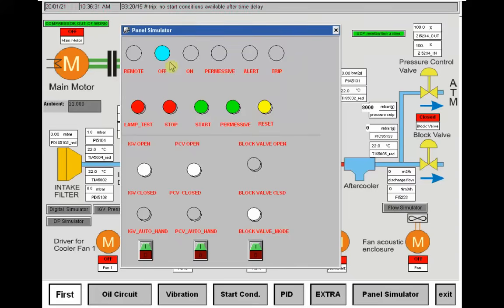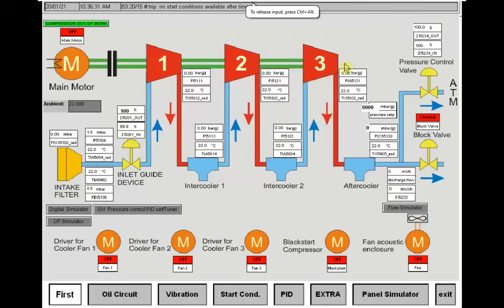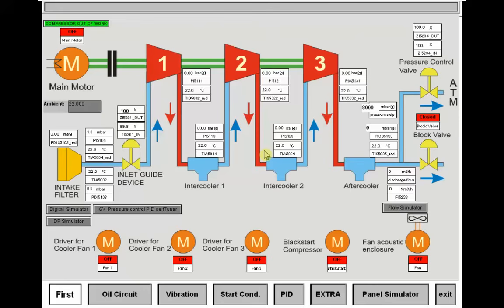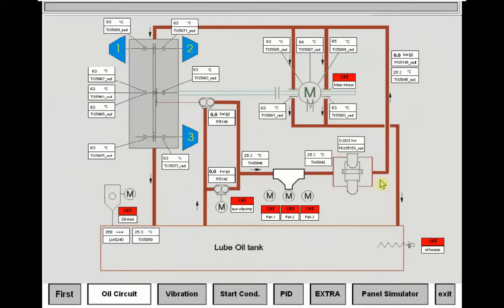So in this simple simulation we tried to function test the importance of oil pressure on the compressor. We simulated what happens if oil pressure is lost when the compressor is running and producing product, and what happens if pressure is lost before we want to start the compressor. In both cases you have some clues and enough information to check your oil circuit and the transmitters for function test and troubleshoot. I hope you found something new here — please subscribe to our YouTube channel, and thank you for watching.